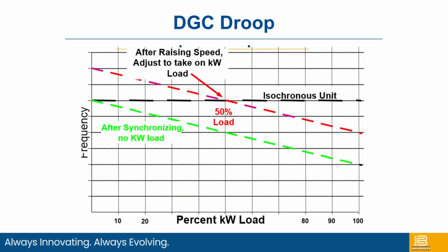We have the ability to program what's called droop. In this industry, what's considered to be droop is basically that as the percentage of load goes up on the gens, both the voltage and the frequency will actually droop down. So you'll start somewhere higher than, let's say, 60 hertz for the US, 50 hertz for others. You'll start at like 62 hertz and end up drooping down to 58 hertz by the time you get to 100% load. Same thing with kVAR.